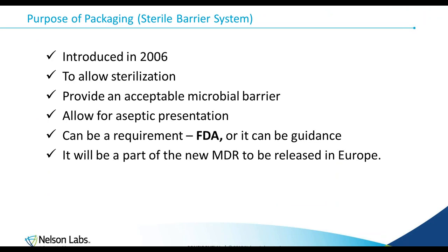So now that we've covered that, let's talk about some standards. The first one really was introduced in 2006, which was ISO 11607. It was to allow for sterilization, provide an acceptable microbial barrier, allow for aseptic presentation, and it is a requirement of the FDA, and soon Europe is going to follow with the MDRs to be harmonized with the ISO 11607.